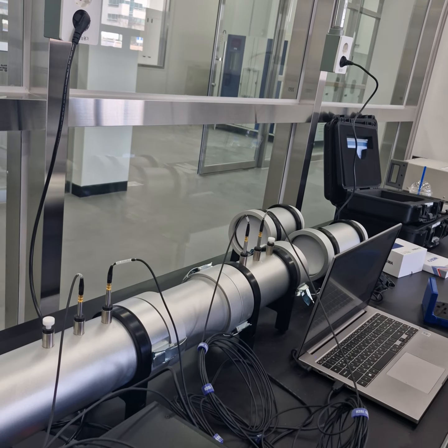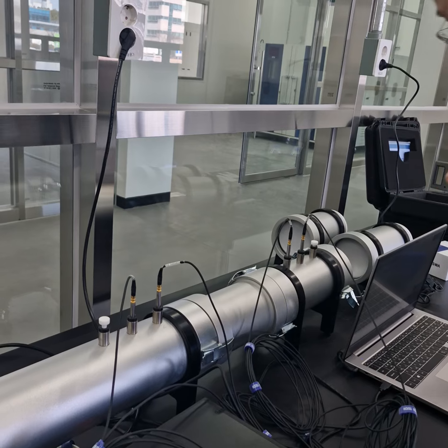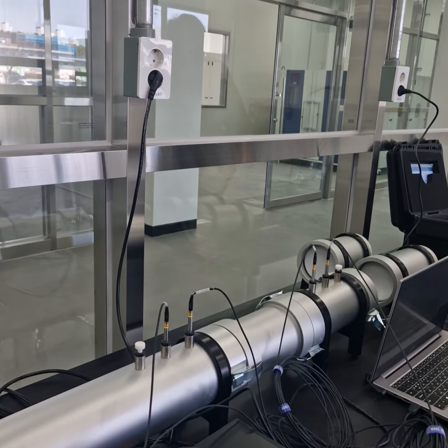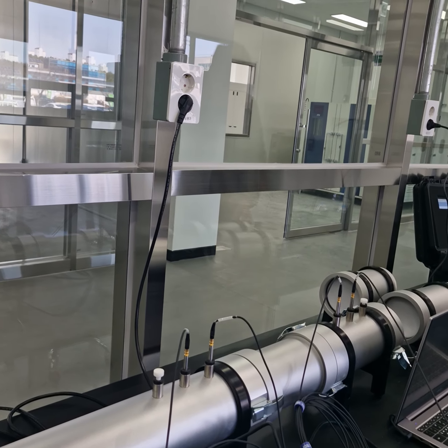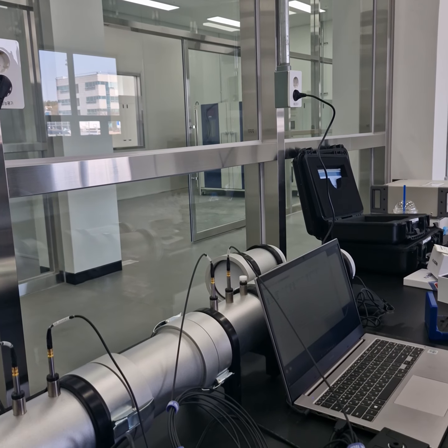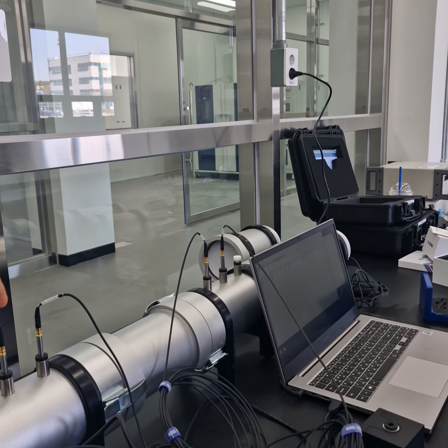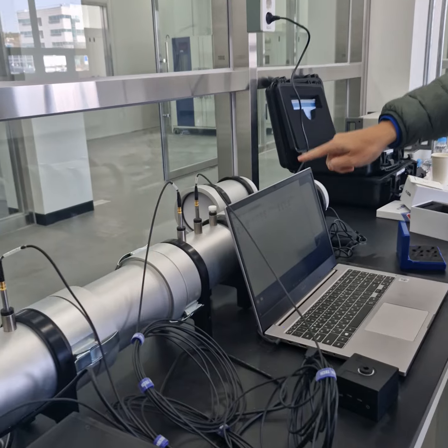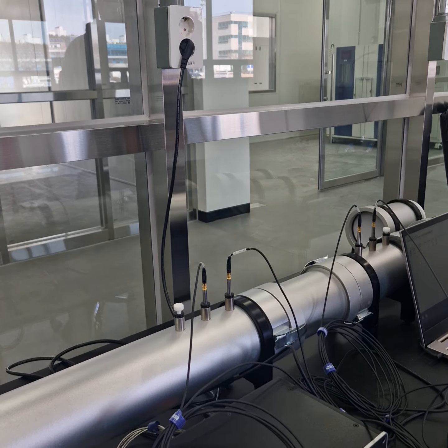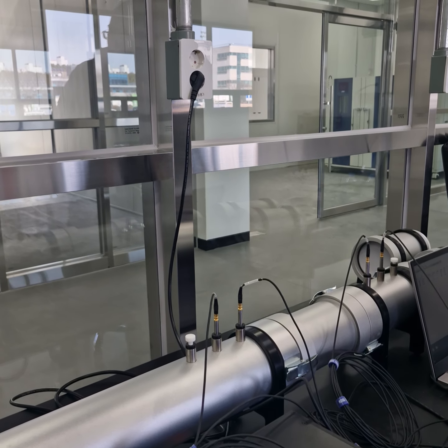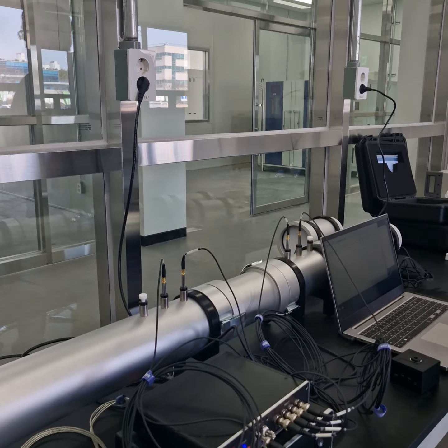We also need to do the sound calibration. Where's the calibrator? Here. The first thing is to do sound calibration. We already did the channel setting and already did the sound calibration, but we are using a new computer, so we need to redo the calibration. And for calibration, in general, we need to do it before every test.